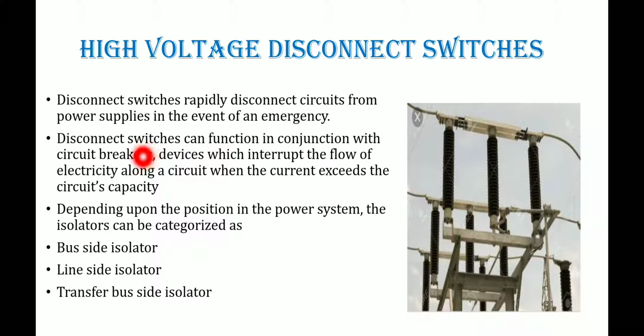So what is the necessity of using both in substations? The disconnecting switch is used in conjunction with the circuit breaker because, although circuit breakers always trip the circuit, the open contacts of the breaker cannot be seen physically.